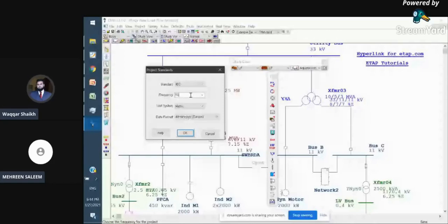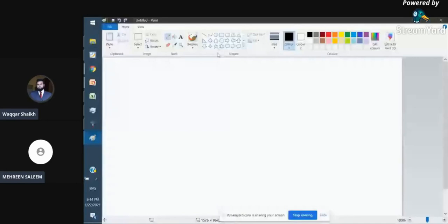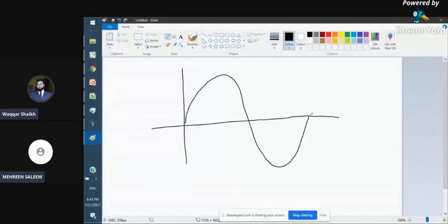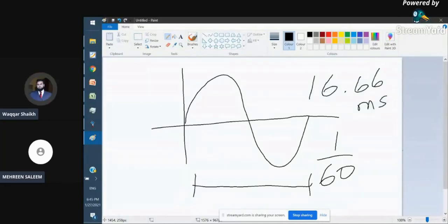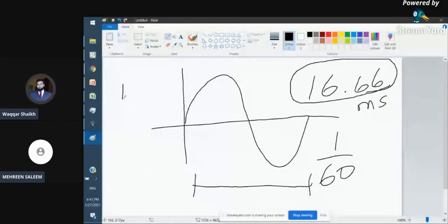A third example of how the frequency impacts your studies is protection studies. Whenever you have a 60 hertz system, let me try to explain by using the Paint software. This is your 60 hertz system. 60 hertz means this waveform will have a time period of 1/60 seconds. If you convert it into decimals, it will be around 16.66 milliseconds. So in the case of a 60 hertz system, we have one cycle length of 16.66 milliseconds. But if we have a 50 hertz system, we will have one cycle equal to 20 milliseconds. This is actually the formula, T equals 1/f. So in this case, you will have a 20 millisecond time period for one cycle.